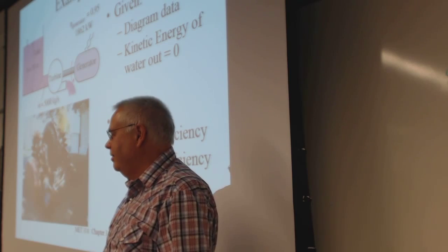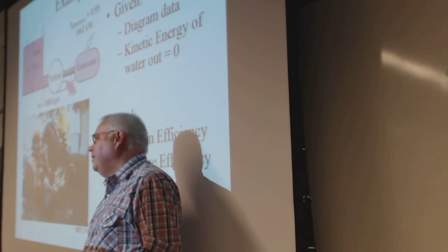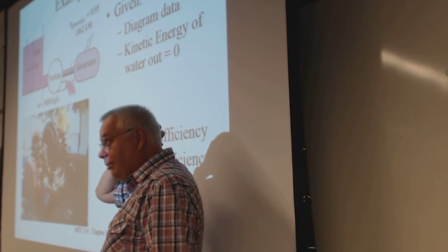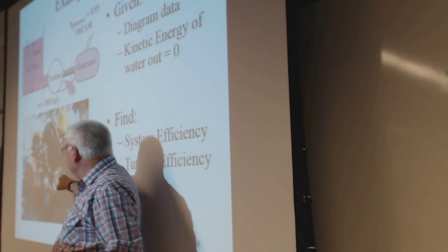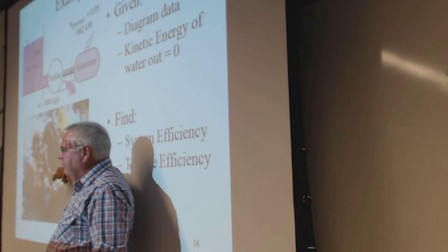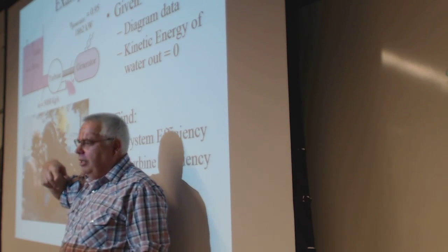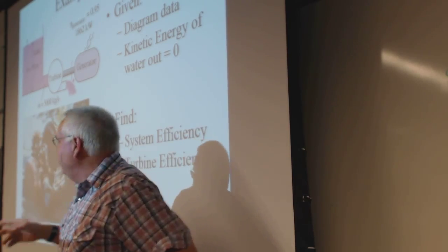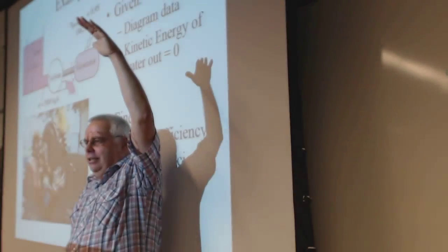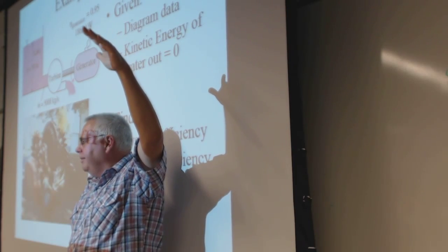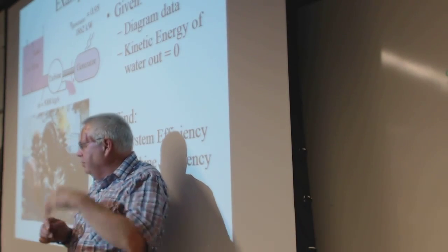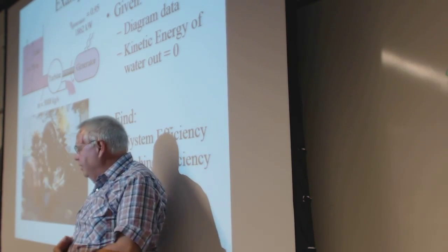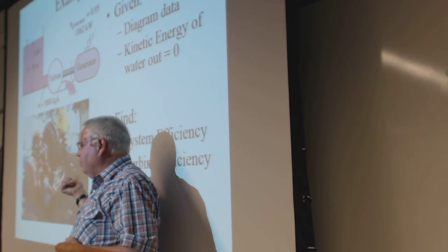All your kinetic energy. Well, yeah, you're able to capture a change in momentum. So they're pretty good. There are modern ones. This isn't just an antique thing. Packwood, on the slope of Mount Rainier, has a generating station that uses these too. What these are good for is high head, like 1,000 feet, high pressure and low flow. You don't have a lot of water, but you've got a lot of elevation. On Mount Rainier, there's Packwood Lake, and that drops down a long ways. That's where these work. They don't work so well in a dam.